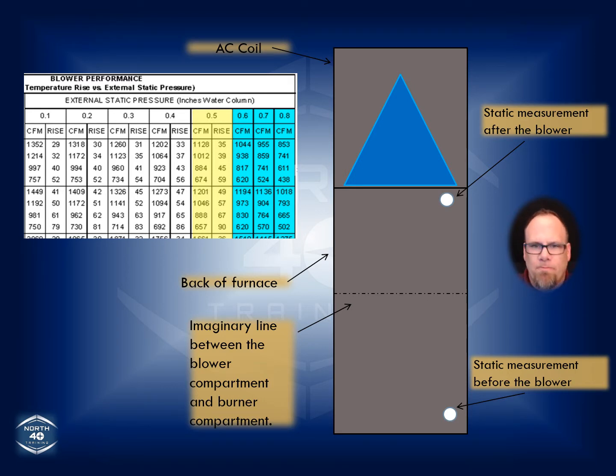So, checking the airflow. Hey, here we are talking about air conditioning systems and checking the airflow. And we hear terms like external static pressure, or ESP, thrown around all the time. So what does that actually mean? Well, ESP, the external static pressure: basically, static is a fancy word for resistance, right? So we're looking for resistance external to that furnace. So everything that is before the furnace, including the filter and all the ductwork, and everything that's after the furnace, including the coil and all the ductwork, are all included in this measurement.